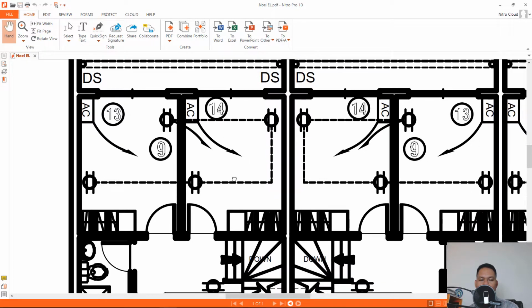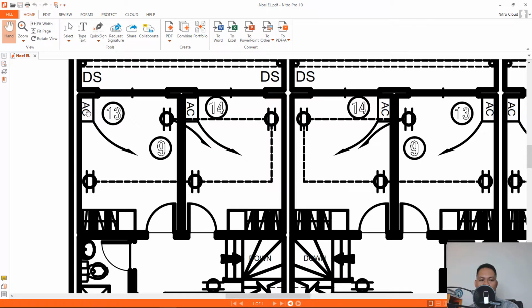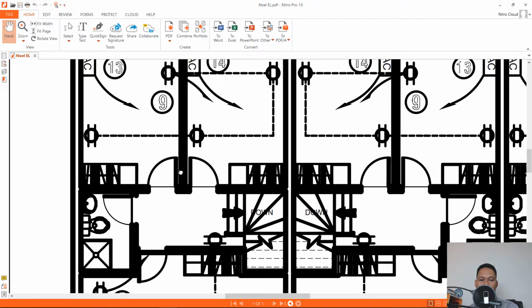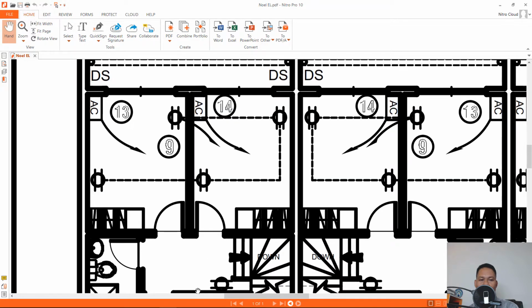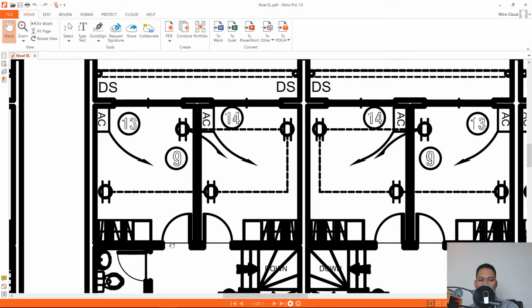This air condition might be a split type, so it's better because you don't need to make an opening on the wall. On this area, maybe this is like 3 by 2.5 meters, so a 1.5 horsepower split type air condition is enough for this one.